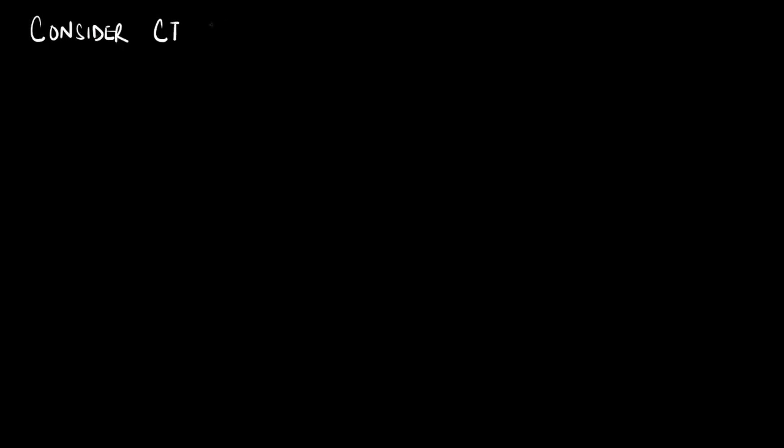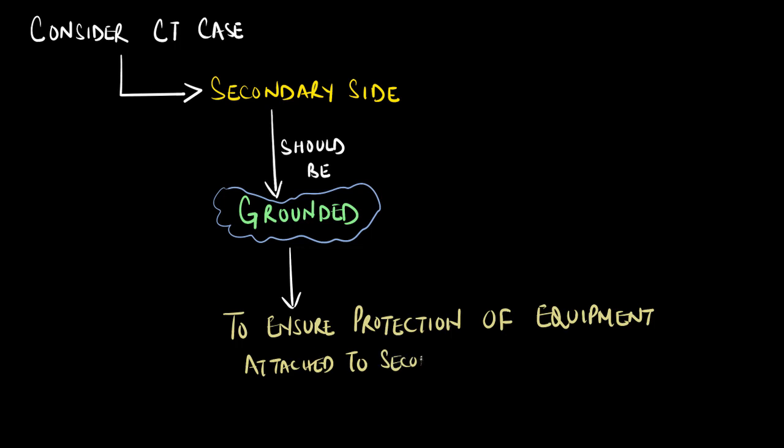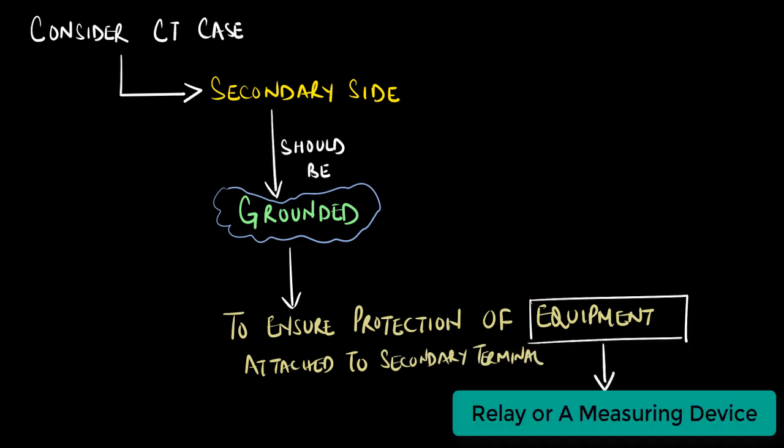If we consider the case of a current transformer, then it is necessary to ground the secondary side in order to ensure protection of the equipment attached to the secondary terminal. The equipment could be a relay or a measuring device.